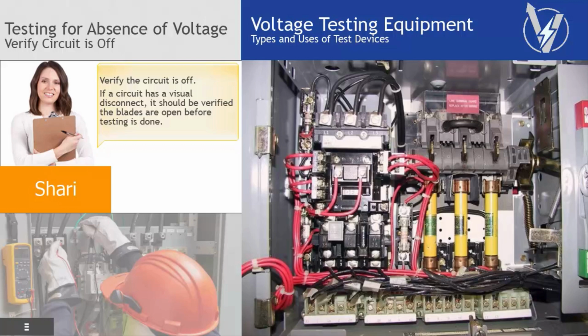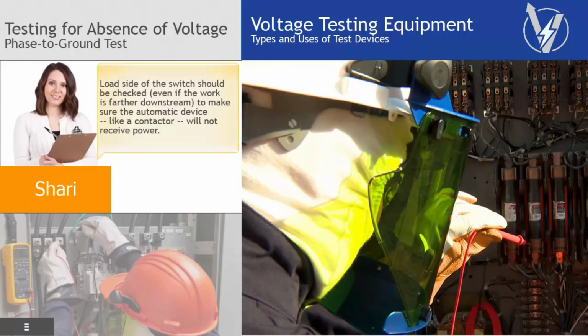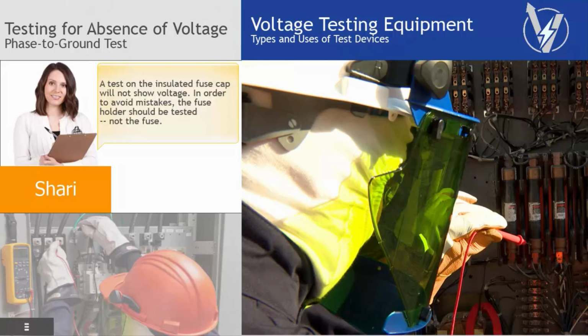Verify the circuit is off. If a circuit has a visual disconnect, it should be verified the blades are open before testing is done. Load side of the switch should be checked, even if the work is farther downstream, to make sure the automatic device, like a contactor, will not receive power. A test on the insulated fuse cap will not show voltage. In order to avoid mistakes, the fuse holder should be tested, not the fuse.